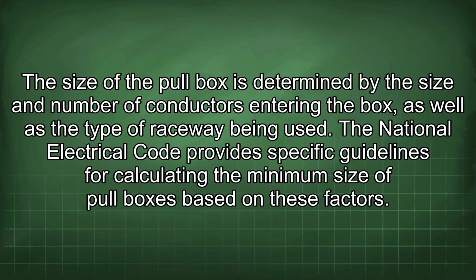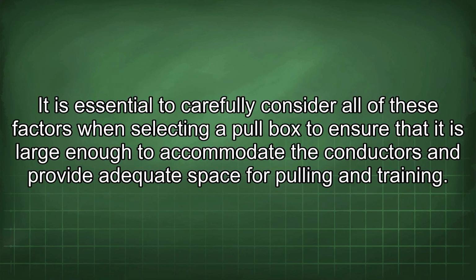The size of the pull box is determined by the size and number of conductors entering the box, as well as the type of raceway being used. The National Electrical Code provides specific guidelines for calculating the minimum size of pull boxes based on these factors. It is essential to carefully consider all of these factors when selecting a pull box to ensure that it is large enough to accommodate the conductors and provide adequate space for pulling and training.